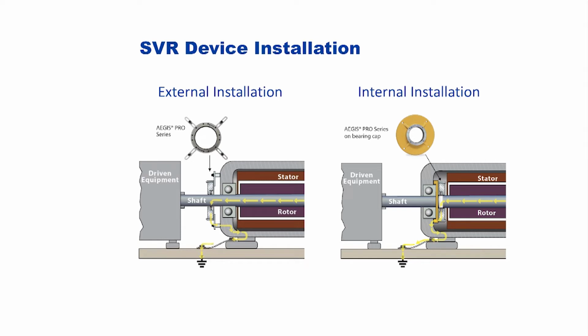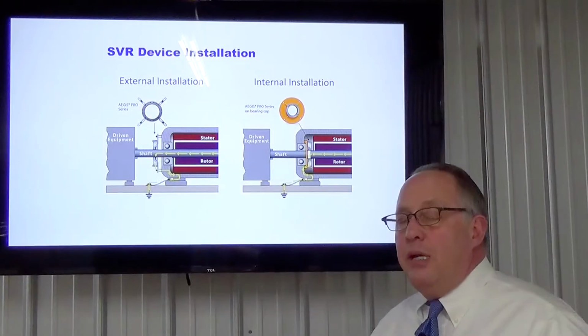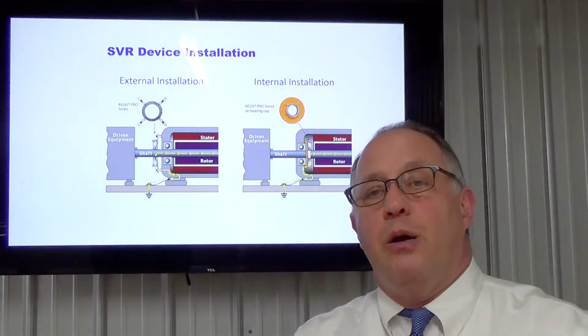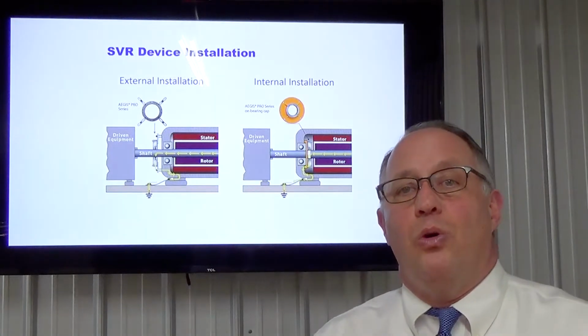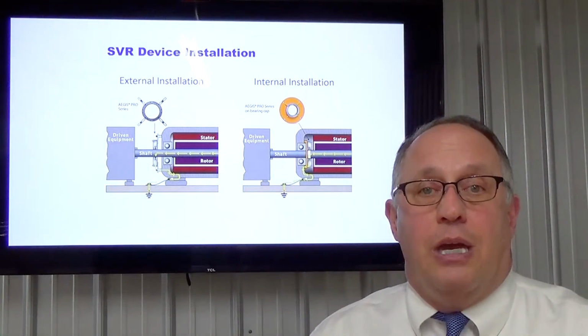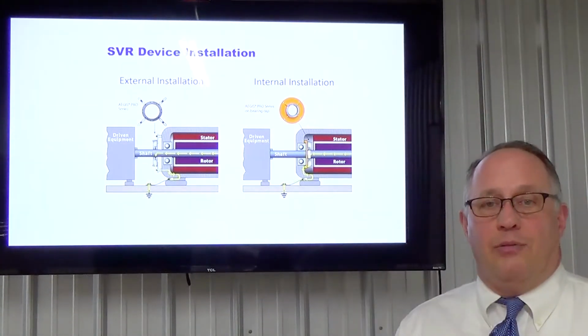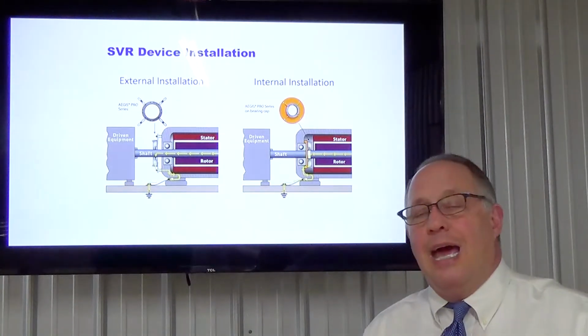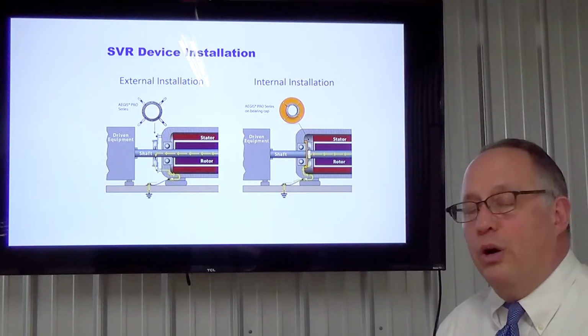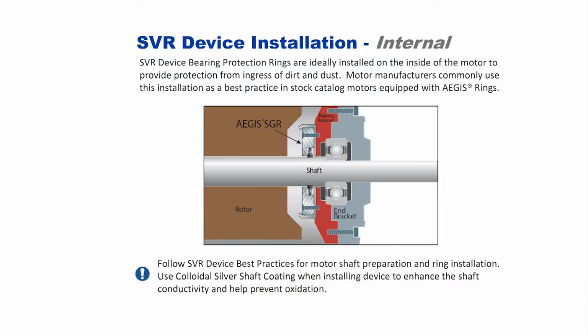The device itself, if you're using this particular type of device, remember I said it could be on the exterior of the shaft, close to the driven equipment, or there are more and more motor manufacturers now that are providing this as an option, where you can get the motor with the shaft voltage reduction ring installed inside the motor directly, so you don't have to worry about contractors or your maintenance staff or anyone having to install that. It's already installed and comes as part of the motor itself. The device installation internal, like I said, is inside the bearing retainer ring and next to the rotor, pre-installed. You can get this shaft protection preparation and ring installation using silver shaft coating while installing the device to enhance the shaft conductivity and prevent oxidation.